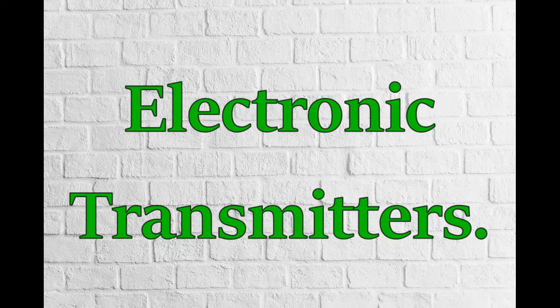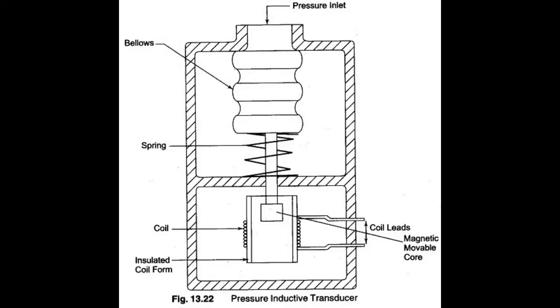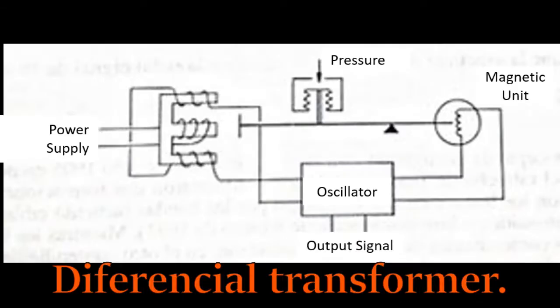Electronic transmitters can base their operation on inductance detectors, differential transformers, Wheatstone bridges, or a force-balance beam, which convert the variable signal into a 4 to 20 mA direct current electronic signal. The problem is that these types of transmitters are sensitive to vibrations and cannot store plant signals.